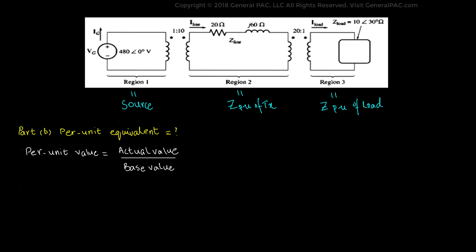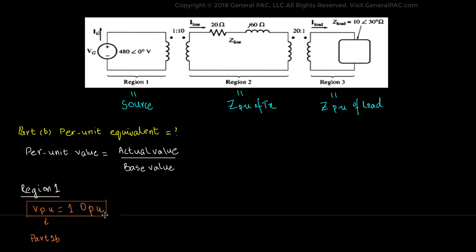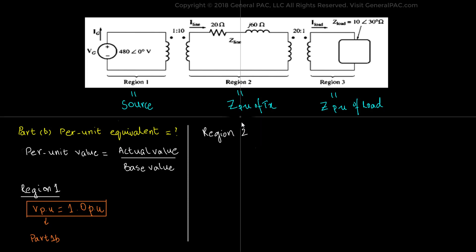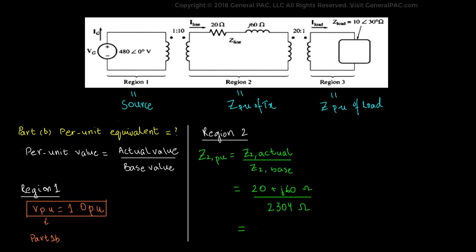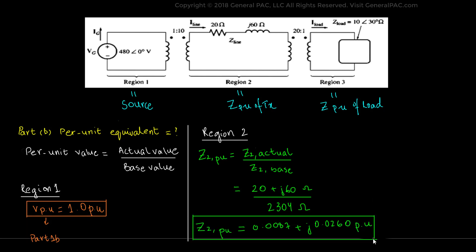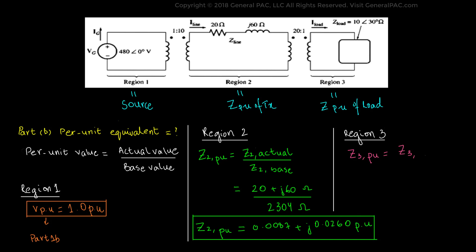For Region 1, we calculated the per unit voltage in Part 1B, which was given as 1 per unit. For Region 2, the per unit impedance of the transmission line is Z2(pu) equals Z2-actual divided by Z2-base. Z2-actual equals 20 + j60 ohms and Z2-base equals 2304 ohms, giving 0.0087 + j0.0260 per unit. For Region 3, Z3(pu) equals Z3-actual divided by Z3-base. Z3-actual equals 10 ohms at 30 degrees and Z3-base equals 5.76 ohms, giving 1.736 at 30 degrees per unit.